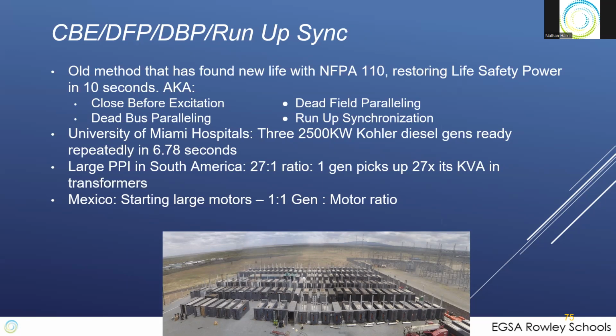The big advantage to them was that they actually could start less. EPRI data says 98% of the outages in the US last less than 2 seconds. If you have a classical system, you can't wait that 2 seconds. As soon as you have an outage, you're starting those gens and you're cranking, because you've got to get there within 10 seconds to meet NFPA 110. So you've got to move fast. With this system, you can wait that 2 seconds, knowing you'll be able to get all 3 online in 6.78 seconds repeatedly. It's a huge savings on starts and cranks.